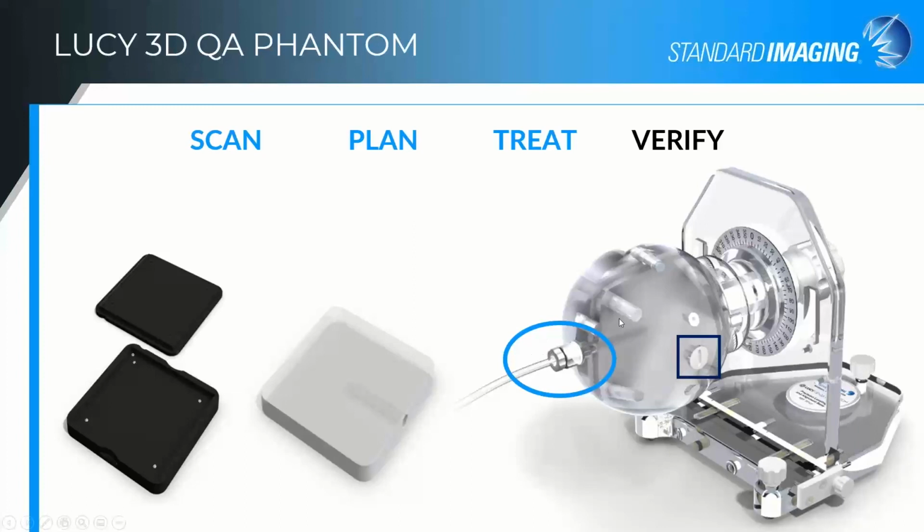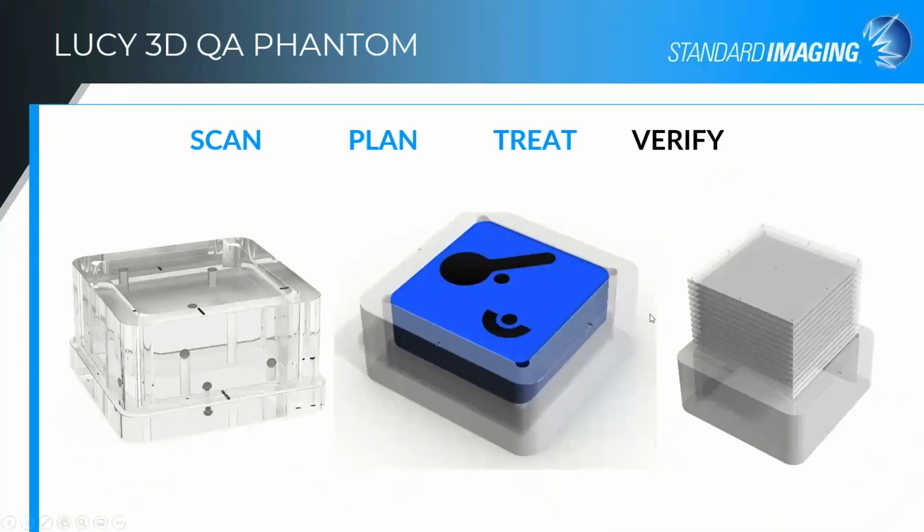And then orientation can be either end on here or from any of the sides for the chamber detector with rotation demarcated, so you can get that set up easily in the different orientations. We also have a Multimets phantom, target and avoidance structures, multiple film stack, different tools there to help you really feel confident in your stereotactic program and your small field deliveries.